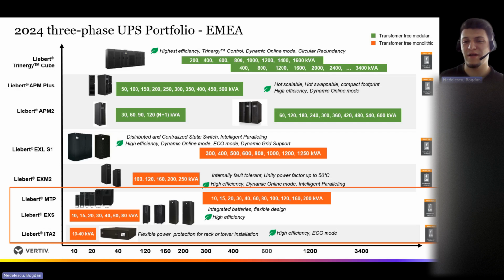Moving forward, as I said in the beginning, we also have three-phase UPS. I want to highlight the most important information about our three-phase UPSs as a fresh reminder. First of all, we're talking about supply voltage that can reach up to 400 volts, and much higher power protection, from 10 kVA up to 3,400 kVA. These UPSs are divided into two technologies: monoblock, or monolithic, UPSs highlighted in orange, and our modular UPSs highlighted in green.